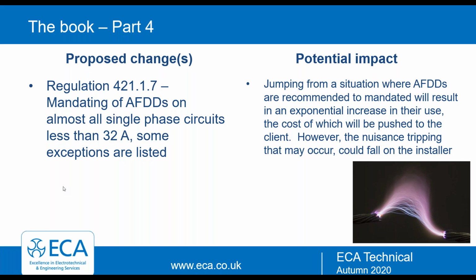Would AFDDs be suited for a shower or cooker rated at 40 amps? Don't think you can get them, can you? That's right, so I think it's just limited. The proposed reg does only talk about things 32 amps or less. So the question, the big issue is that the larger current draw circuits like showers, 32 amps or more, are likely to cause the biggest problems. Also, can they be tested like an RCD?